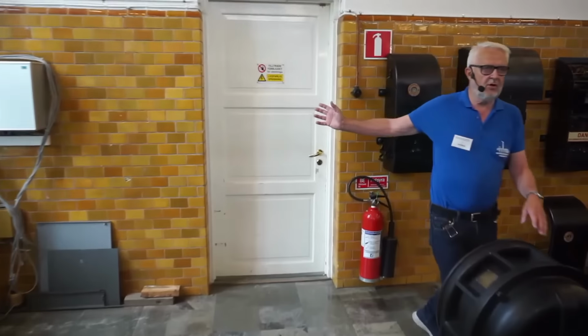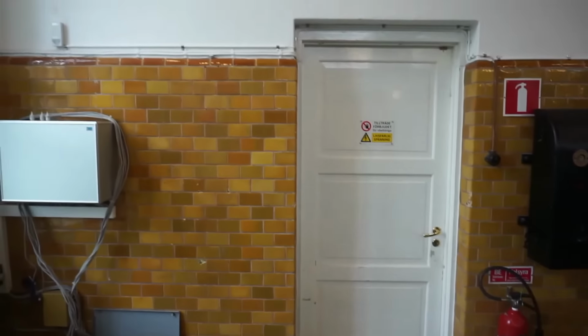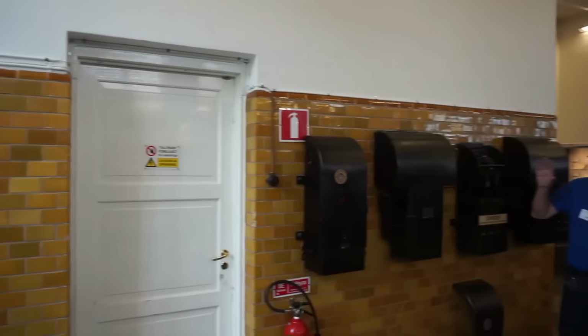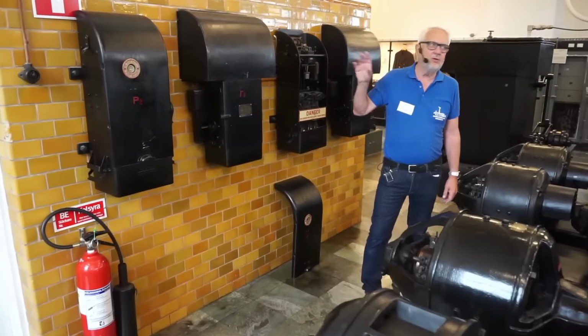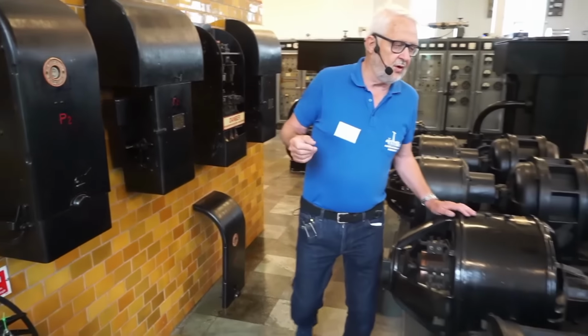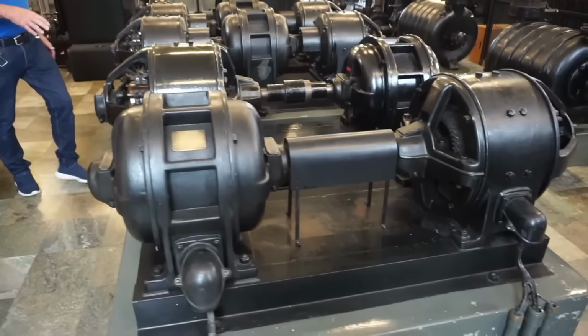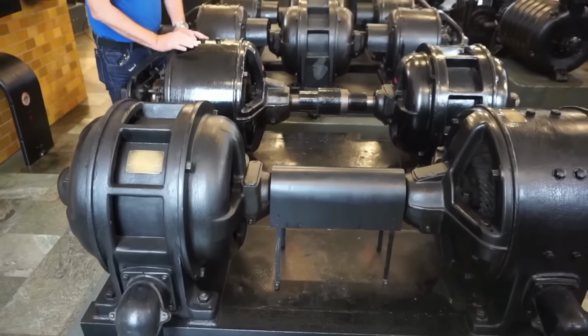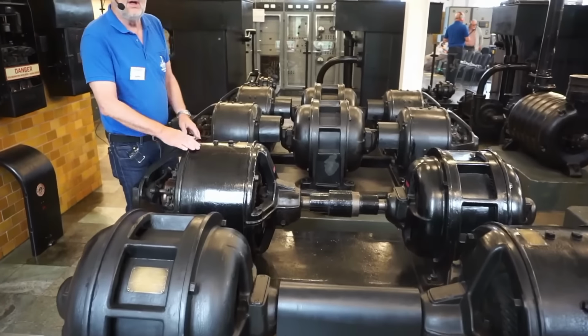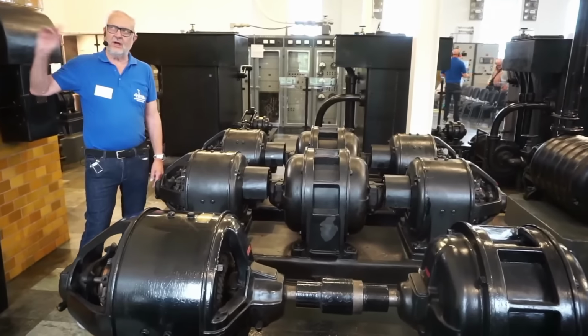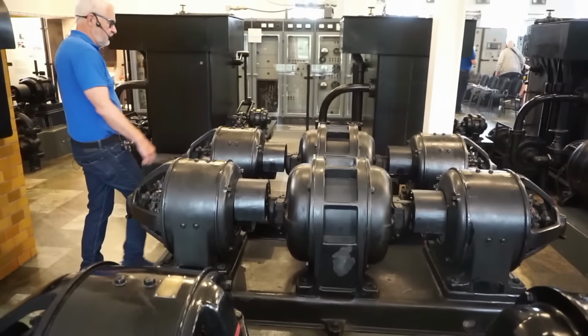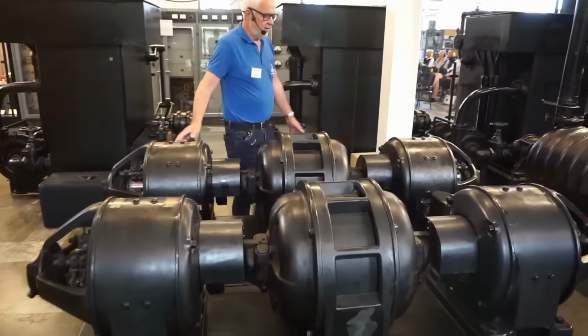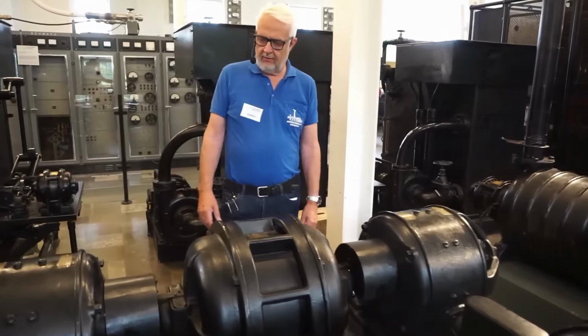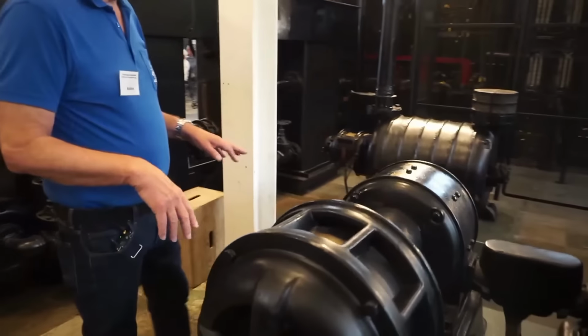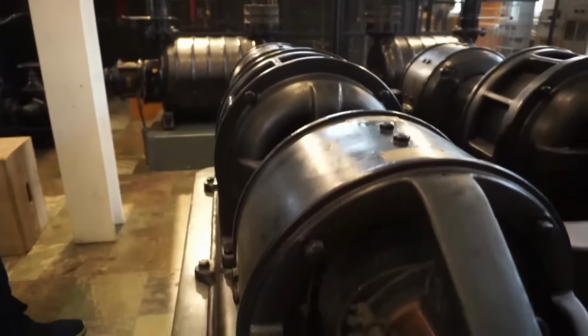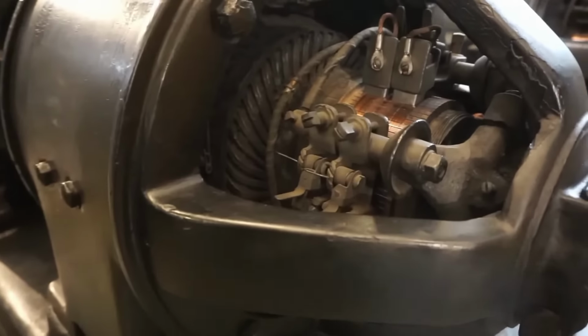Behind me here we have the transformer room where the power comes into the station. There are also 4 transductors that can control the power, the voltage to the main motor. There are also a set of transformers for the main voltage. Here we have a set of rectifiers that provides 500 volt DC, and it is controlling the transductors in the transformer room. One is a backup. Here we have a set of transformers that gives 125 and 250 volt DC. That is used for the relays and for magnetizing, amongst others, the high-frequency generator.